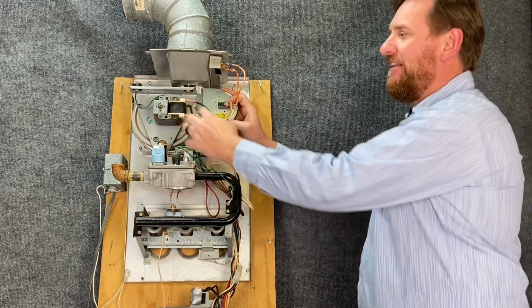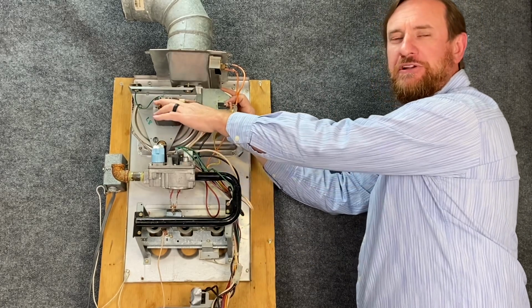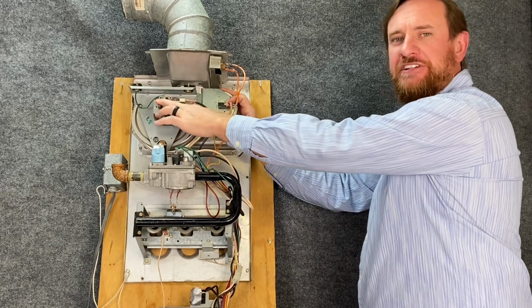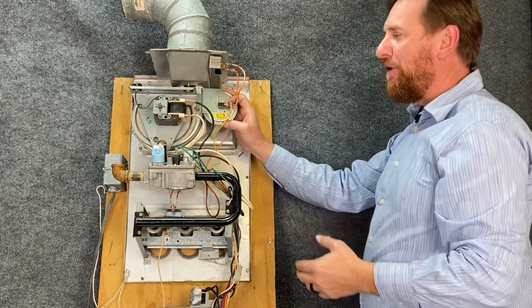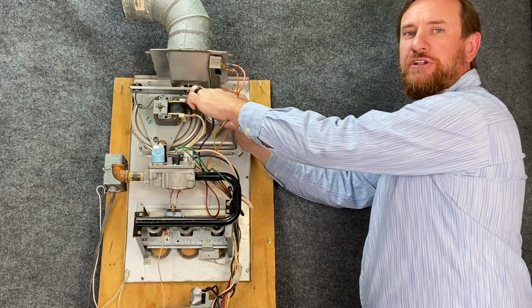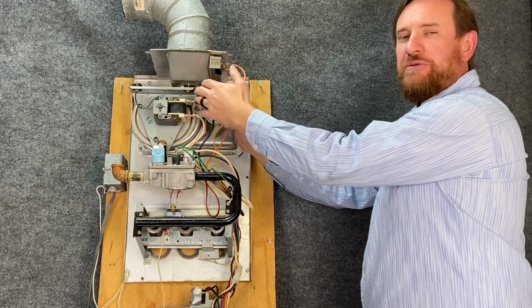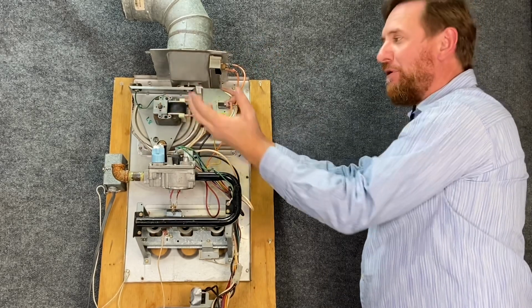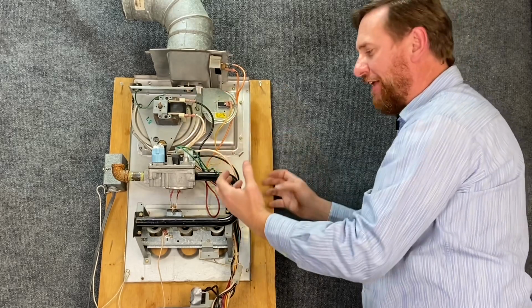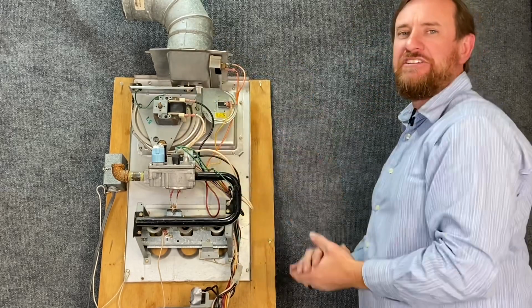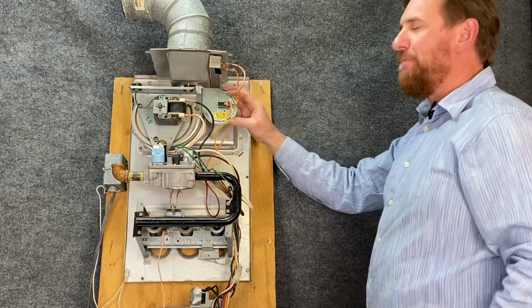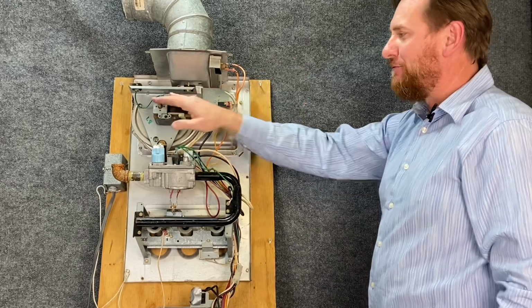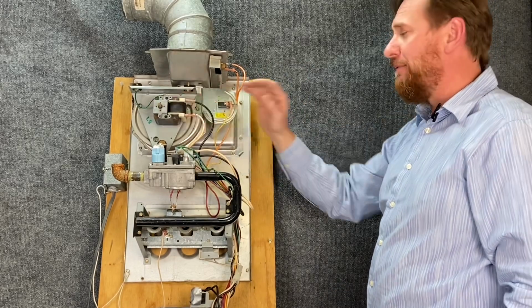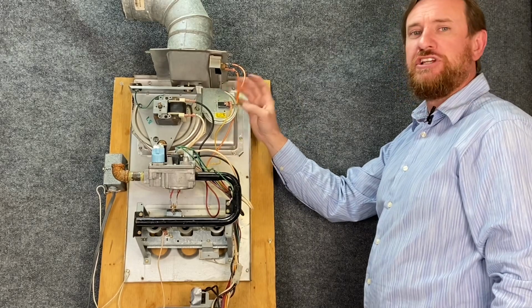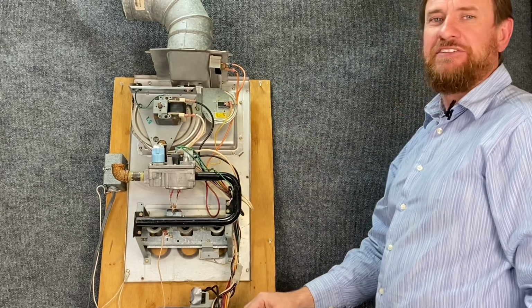In the old days, they had centrifugal switches on these motors. So when the motor spun fast enough, the switch would close. The problem we had was these old motors would rust out. There'd be some kind of an issue with it. The switch would close, but it wasn't actually pulling a draft. The flame would roll out of the heat exchanger and catch the system on fire. So this was the better system that was invented. As this motor is pulling a draft, doing its job, it pulls a vacuum to this pressure switch, the switch closes, and tells the IFC it's working.